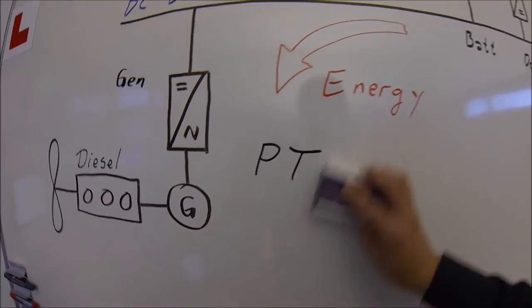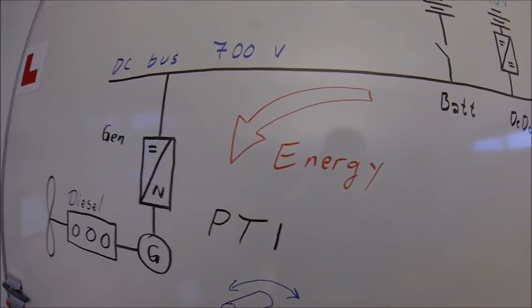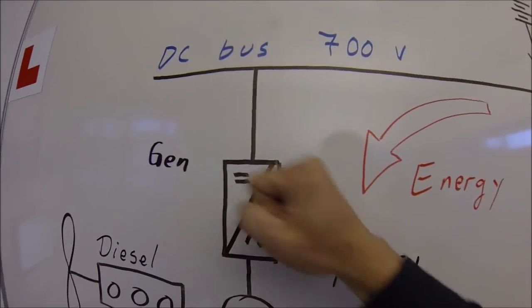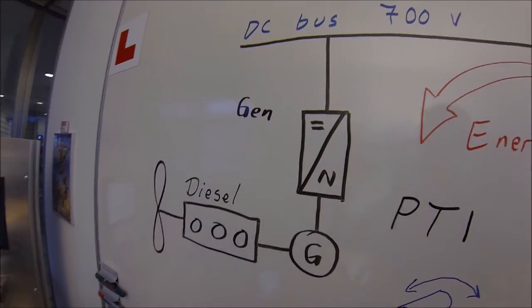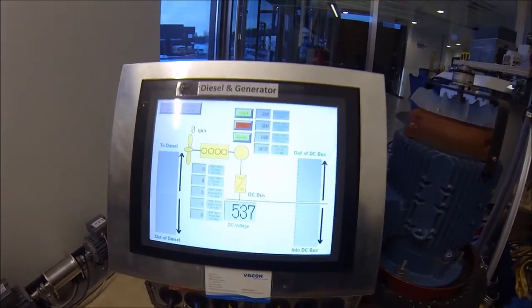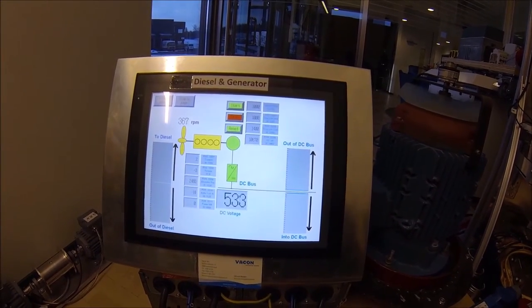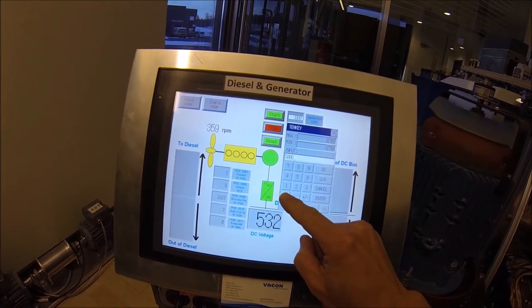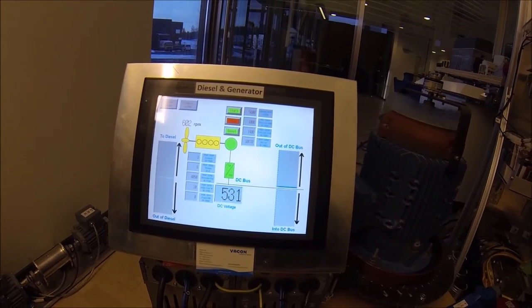For navigating the ship, power take-in mode is a more controlled approach. Changing to power take-in mode moves the power handle and control of the ship propeller over to this side. From the PLC, the power management can give a speed reference with torque limits and power limits to the ship propeller. Now the DC voltage doesn't mean much as long as it is enough — you could start it even at a very low voltage and it will sit running on its speed reference. It will be running with a power handle from the bridge so the skipper is in control.